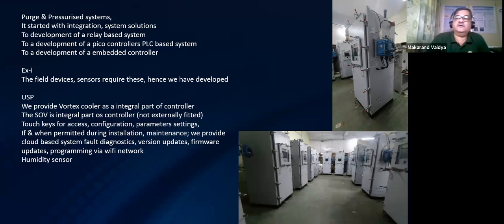In this control panel, there are switching devices like contactors and switches, and every switching action involves some spark, accidentally or otherwise. Those sparks may cause combustion or fire, so this has to be taken care of - hence the humidity sensor and the VOC sensor.